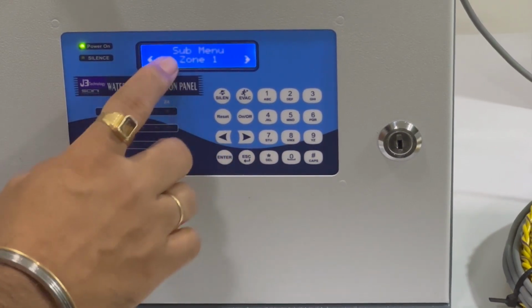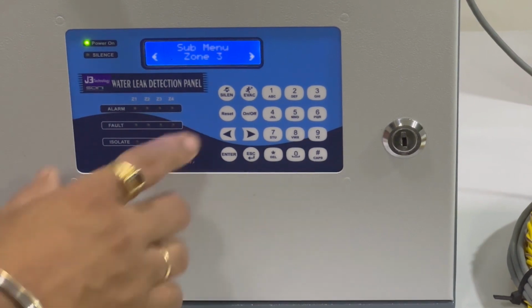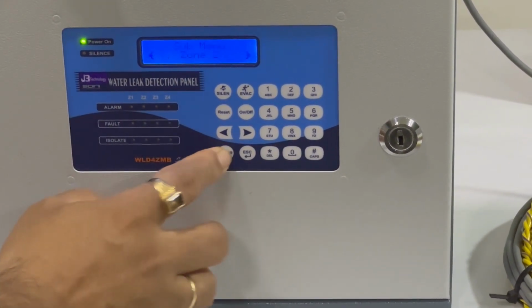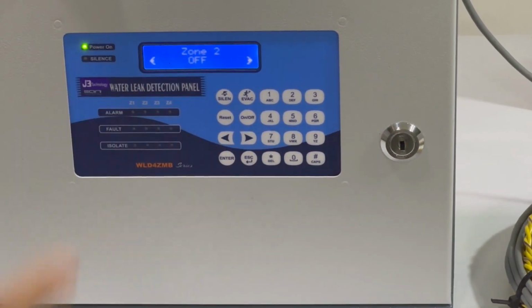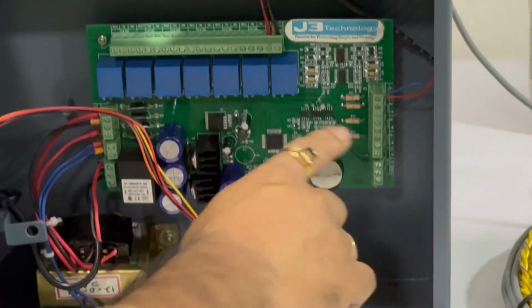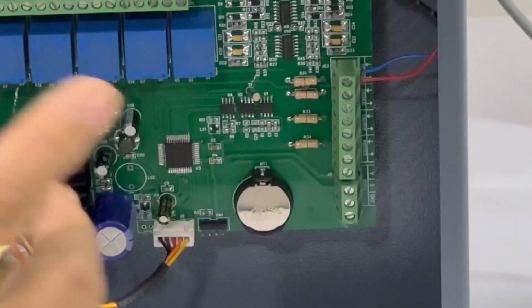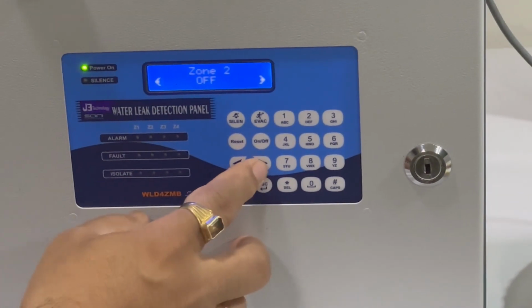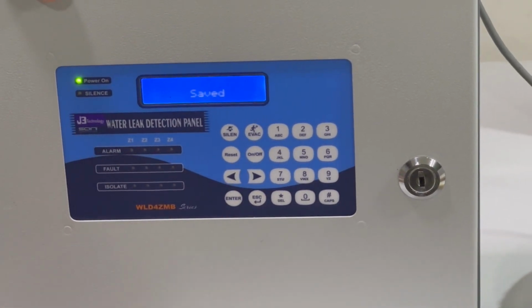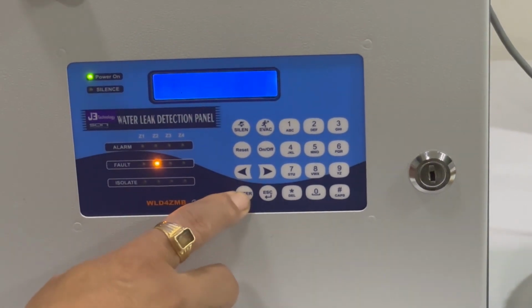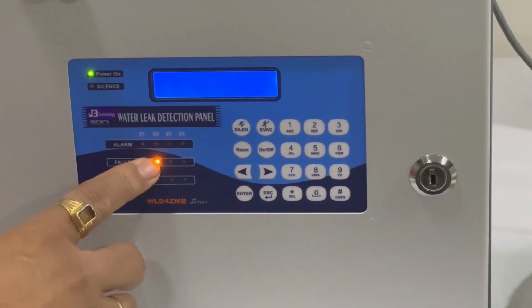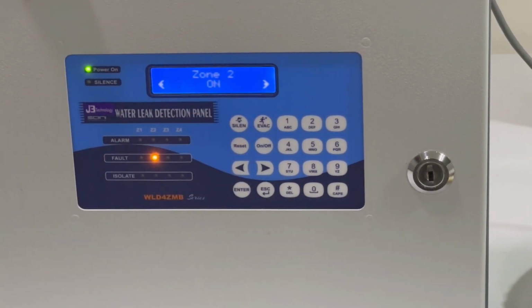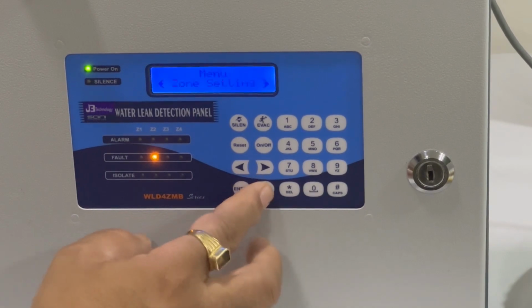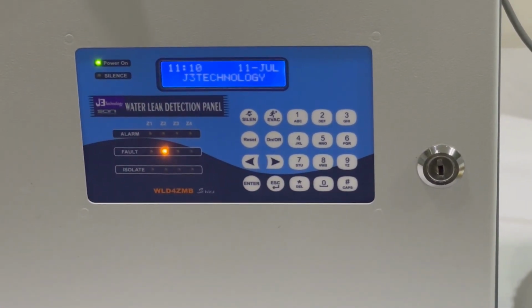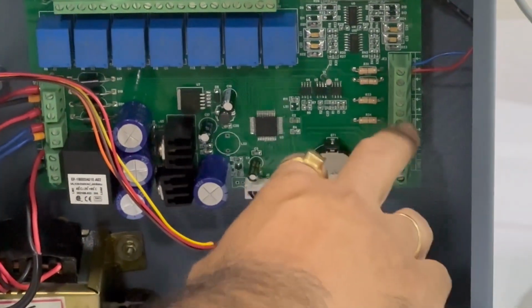Okay, now again you have to go back, and again to zone setting, and go to zone 2. By default it is off because no sensor cable is connected in zone 2. No sensor cable is connected. Suppose I keep it on, just I will show you. I kept it on and pressed enter. See, there will always be a fault indication shown on the front display, and the panel will continually beep that there is a fault in your panel, because you have not used zone 2, zone 3 or zone 4.